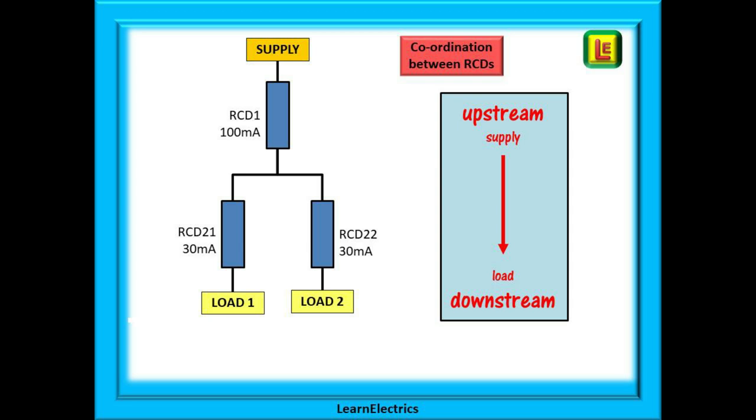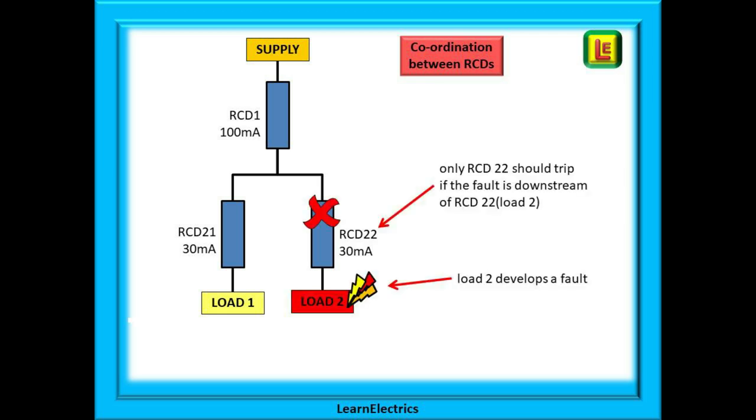If we have a circuit protected by a 100 milliamp RCD with two 30 milliamp RCDs downstream of it we can see that RCD 21 in this example is protecting load number one and RCD 22 is protecting load number two. If a fault should develop in load number two only RCD 22 should operate. RCD 1 should remain in the on position and continue to supply power to RCD 21 and load number one since this part of the installation does not have a fault. We only want load number two to be disconnected.